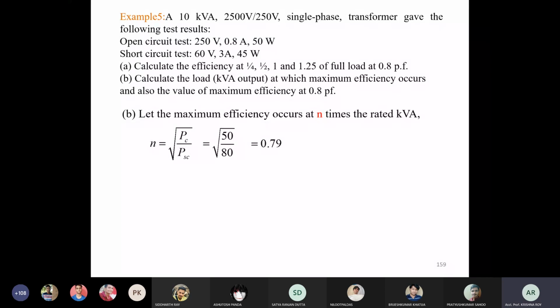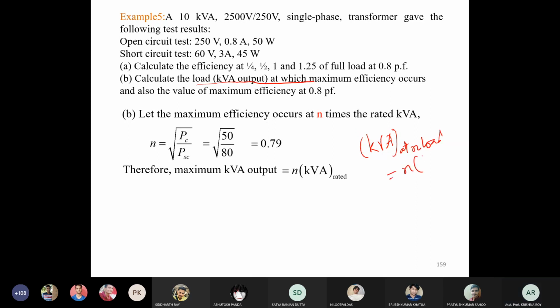Now you have to calculate the load kVA output at which maximum efficiency occurs. So you require this formula: kVA at n load is equal to n into rated kVA. So that is equal to 7.9, because the rated kVA is 10, and 10 into 0.79 is 7.9.